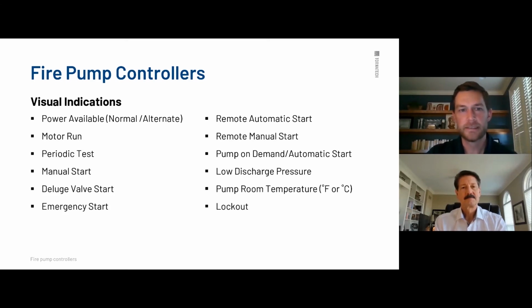But the power available, the motor run, periodic test, manual start. So that's one thing that we didn't have on the screen. Whenever you start the panel or start the pump, the panel is going to display how it was started. So if it was started manually, it'll say manual. If it was started on a pressure drop or whatever other automatic means, it'll say automatic.